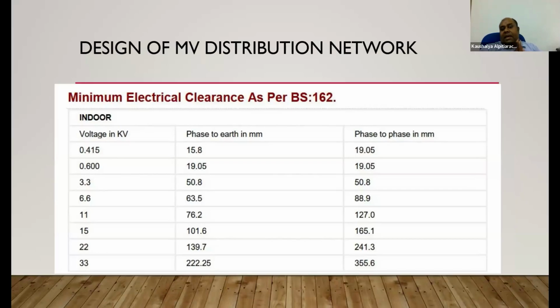Clearances. Minimum electrical clearances. The standard is BS 162. Yes, BS 162 provides you almost all the required clearances for indoor applications, outdoor applications, from building to transmission lines or distribution lines, whether they are bare or insulated, and so on. Vertical distances, horizontal distances, and all. So against voltage in kV, phase to earth in millimeter, phase to phase in millimeter is demonstrated.